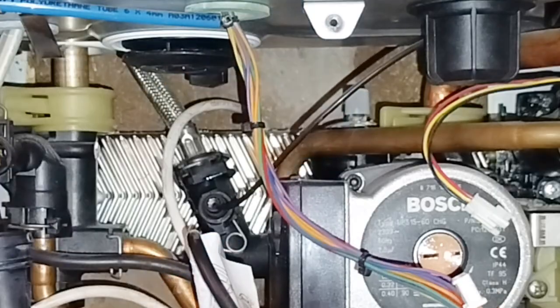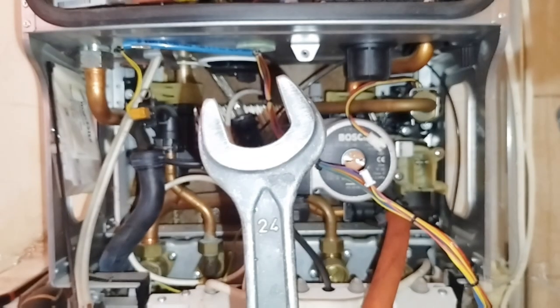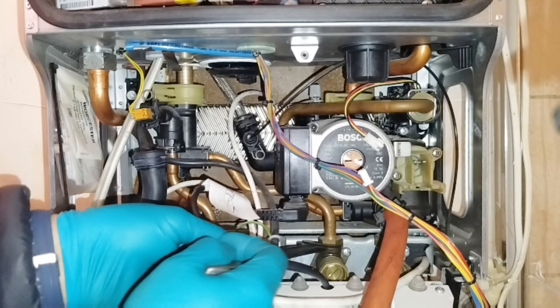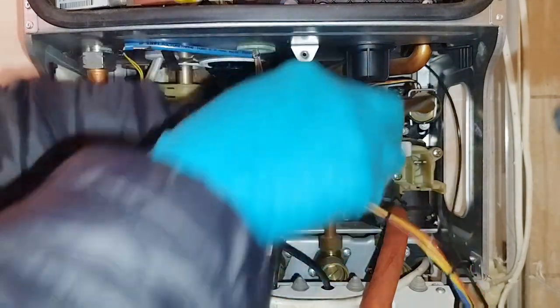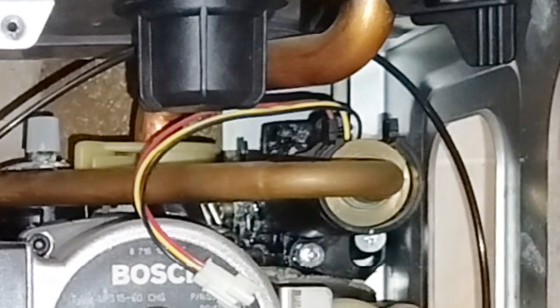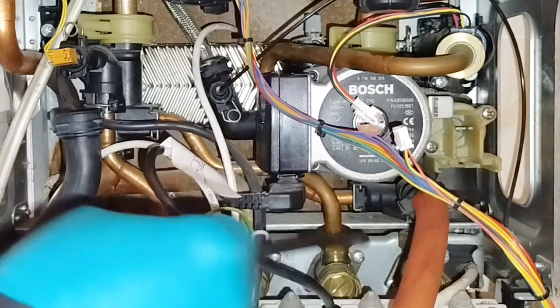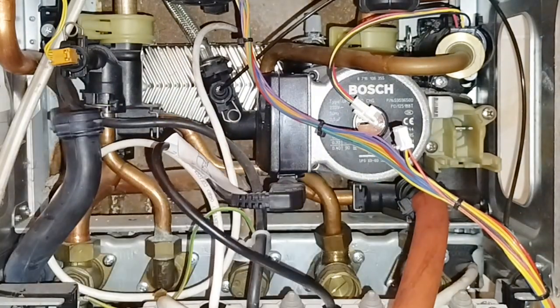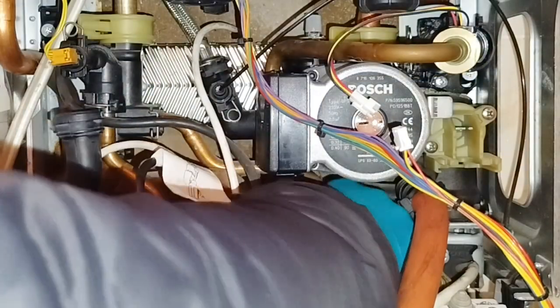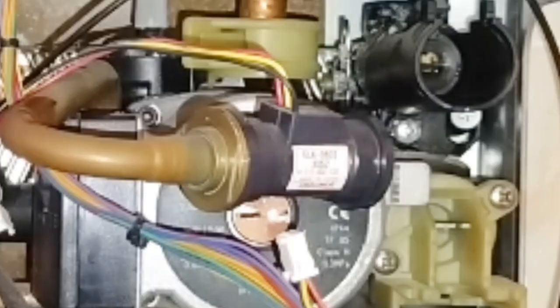We've opened the AAV, the automatic air vent. This spanner, which is 24 millimeters, is usually good for a 15 millimeter nut, be it any compression joint, and loosen that up, and always keep a hot water tap on beside it to be able to drain off any water in the cold water and hot water circuit. Undo the nut slowly, and after it's drained down, then pull the pipe from where the flow turbine sits on the top right hand corner. Further loosen the nut, always slowly to start with to allow the water to drain away through the taps, and slowly and gradually remove the flow turbine assembly with the pipe on the cold water side of things.